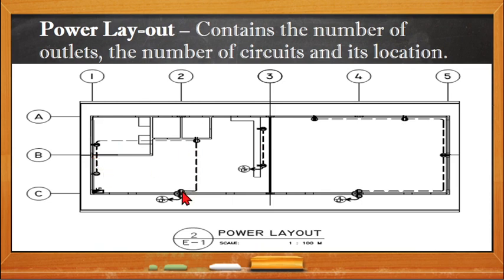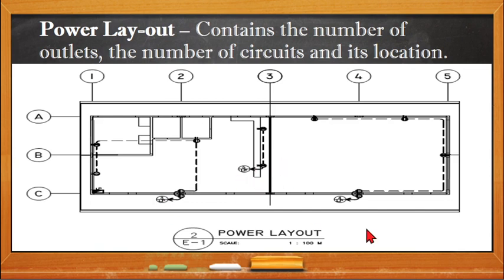As you can see, we have 13 outlets in this example. They are divided into three circuits, because we have the symbol for the home run, and each home run is equivalent to one circuit. Each circuit in the plan will be equivalent to one circuit breaker. This is the symbol for the location of the panel board.